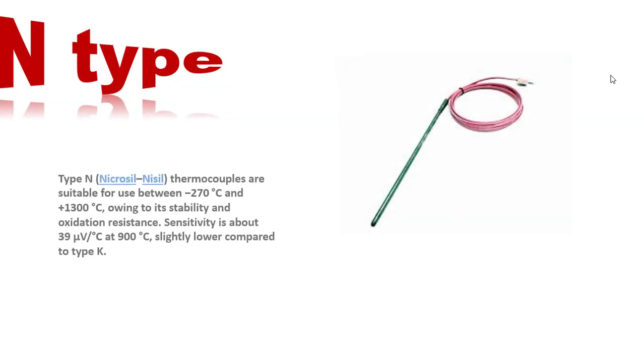Type N thermocouples are suited for use between -270°C and +1300°C due to their stability and oxidation resistance. Sensitivity is about 39 µV per °C at 900°C, slightly lower compared to Type K.